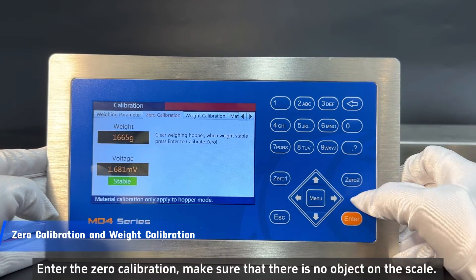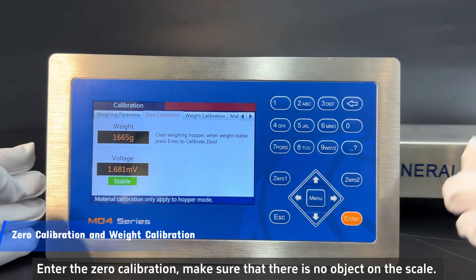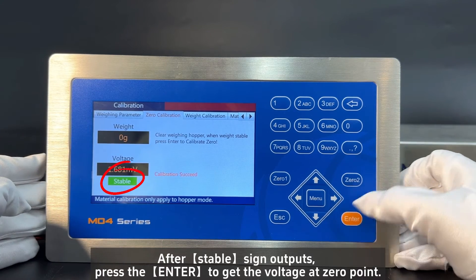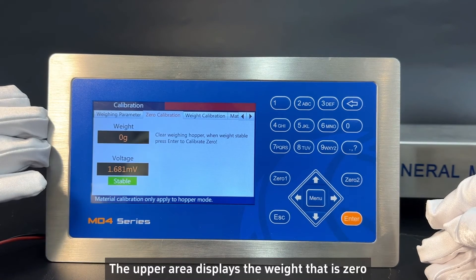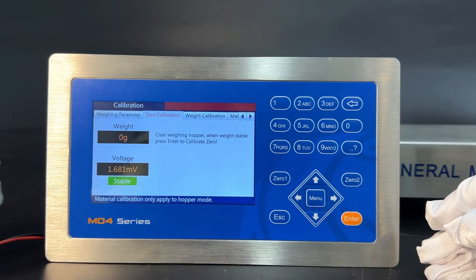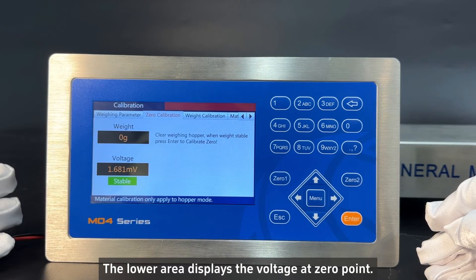Enter the zero calibration. Make sure that there is no object on the scale. After stable sign outputs, press the enter to get the voltage at zero point. The upper area displays the weight that is zero. The lower area displays the voltage at zero point.